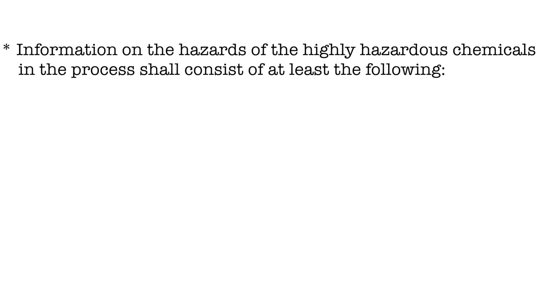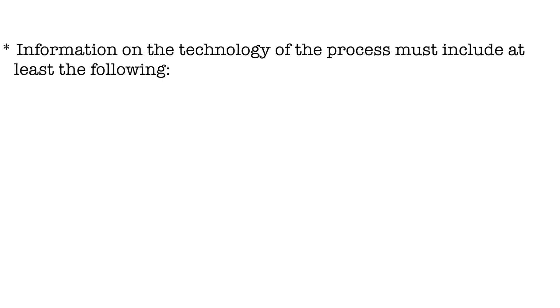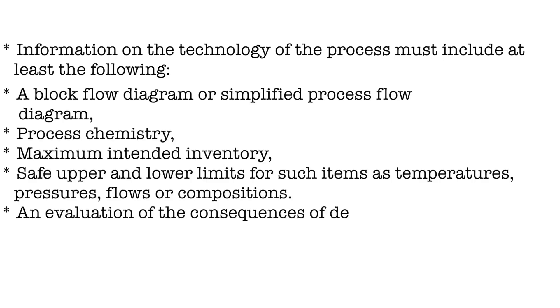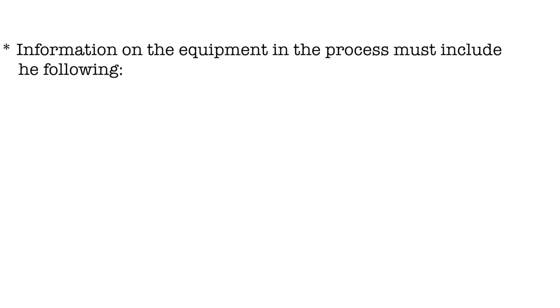Information on hazards of the highly hazardous chemicals shall consist of at least: toxicity information, permissible exposure limits, physical data, reactivity data, corrosivity data, thermal and chemical stability data, and hazardous effects of inadvertent mixing of different materials. Information on the technology for the process must include at least: a block flow diagram or process flow diagram, process chemistry, maximum intended inventory, safe upper and lower limits for temperature, pressure, flow, and composition, and evaluation of the consequences of deviations affecting the safety and health of employees.